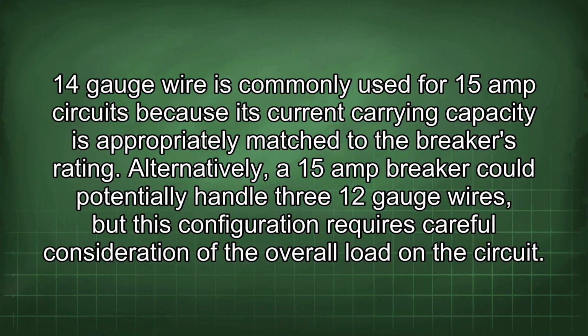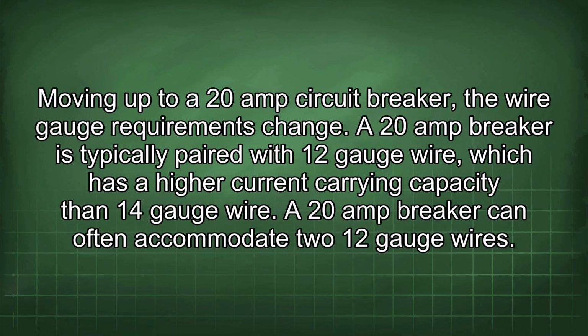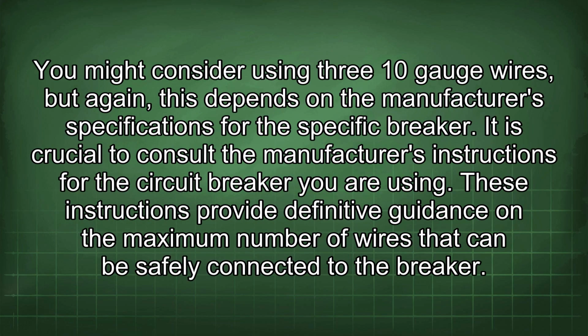in the circuit. Moving up to a 20-amp circuit breaker, the wire gauge requirements change. A 20-amp breaker is typically paired with 12-gauge wire, which has a higher current carrying capacity than 14-gauge wire. A 20-amp breaker can often accommodate two 12-gauge wires. You might consider using three 10-gauge wires, but again, this depends on the manufacturer's specifications for the specific breaker.